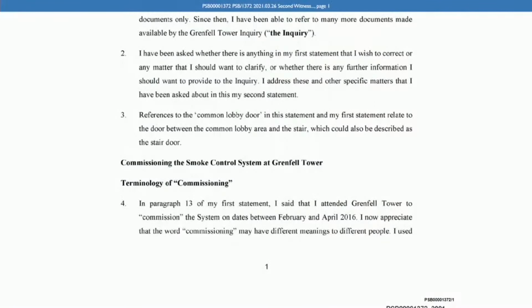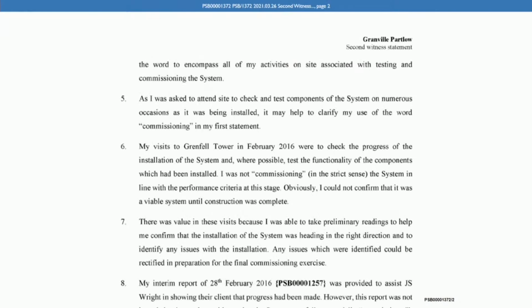Now, if we can go to paragraphs 4 to 6 of your second statement at page 2 of that. And you tell us this in paragraphs 4 to 6, and it's headed Terminology of Commissioning. In paragraph 13 of my first statement, I said that I attended Grenfell Tower to, quotes, commission the system on dates between February and April 2016. I now appreciate that the word commissioning may have different meanings to different people. I used the word to encompass all of my activities on site associated with testing and commissioning the system. As I was asked to attend site to check and test components of the system on numerous occasions as it was being installed, it may help to clarify my use of the word commissioning in my first statement.